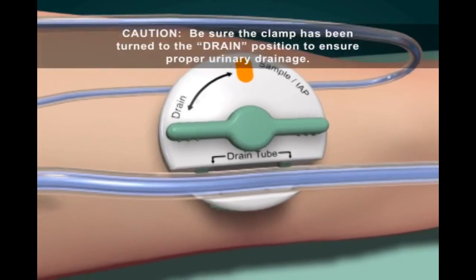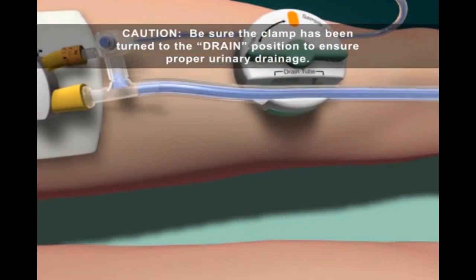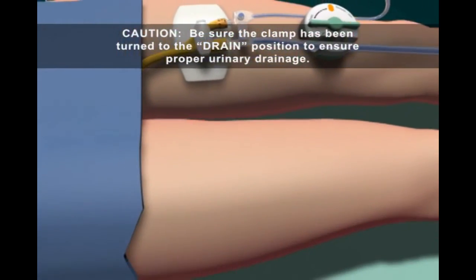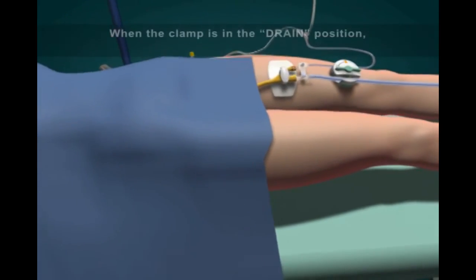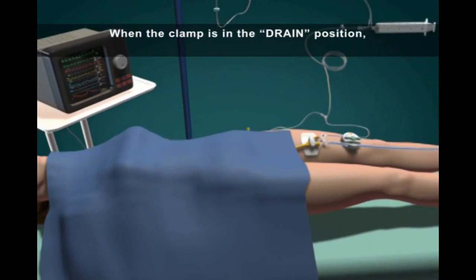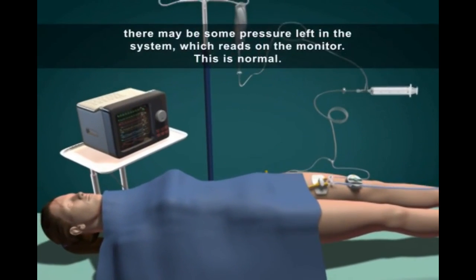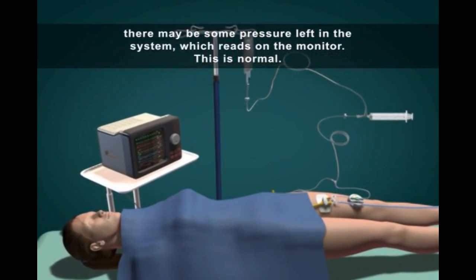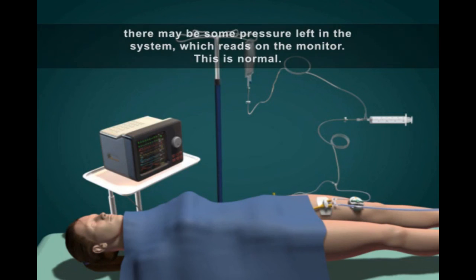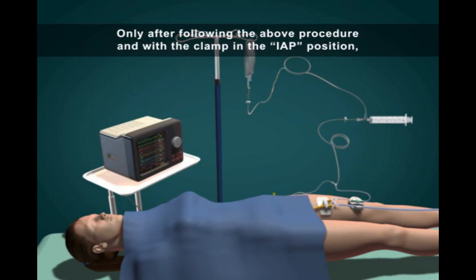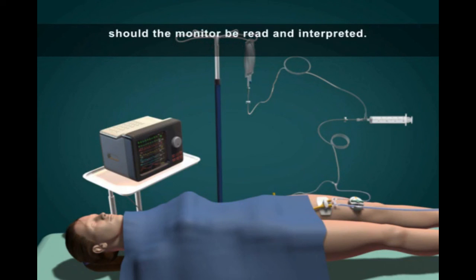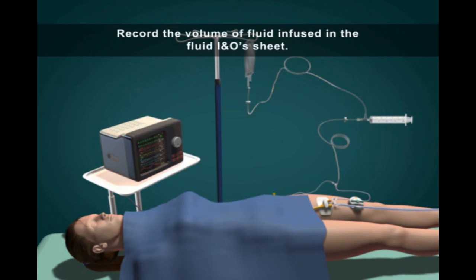Caution: be sure the clamp has been turned to the drain position to ensure proper urinary drainage. When the clamp is in the drain position, there may be some pressure left in the system, which reads on the monitor. This is normal. Only after following the above procedure and with the clamp in the IAP position should the monitor be read and interpreted. Record the volume of fluid infused in the fluid I&O sheet.